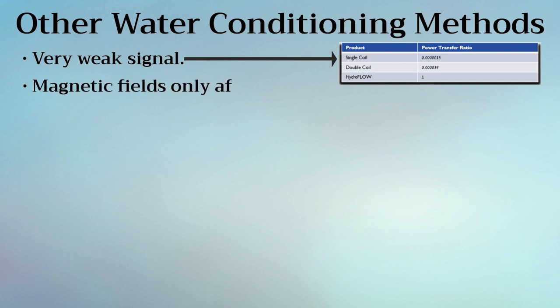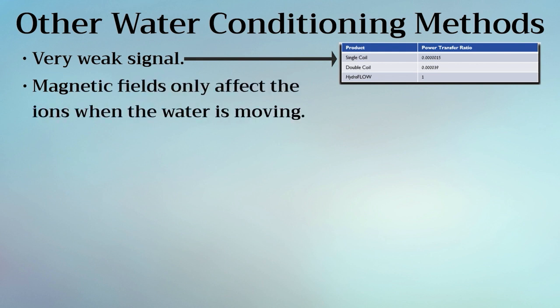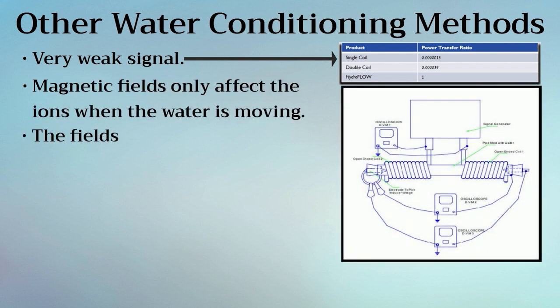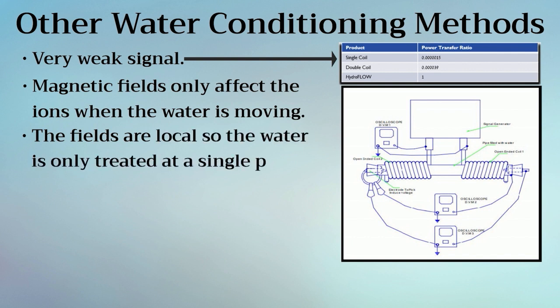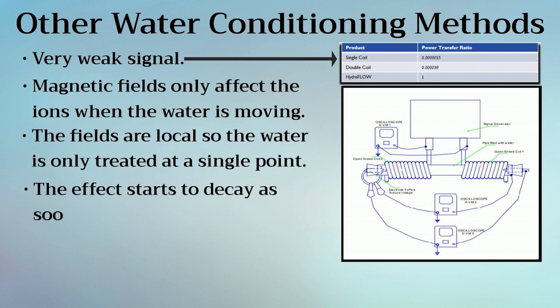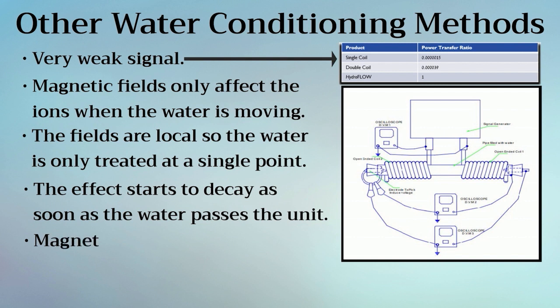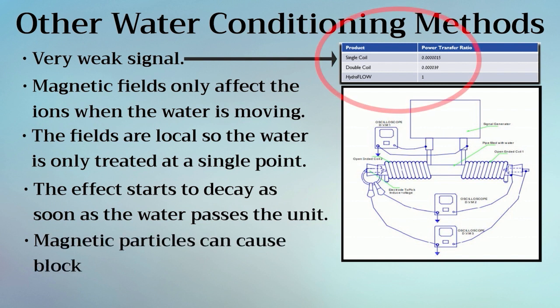Magnetic fields only affect the ions when the water is moving. The fields are local, so the water is only treated at a single point. The effect starts to decay as soon as the water passes the unit. Magnetic particles can cause blockages. Note the diagram on the right showing that HydroFLOW has roughly 30,000 times more output when compared to a double coil wire wrap device.